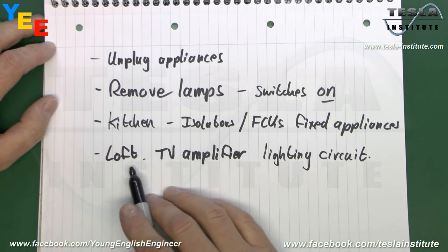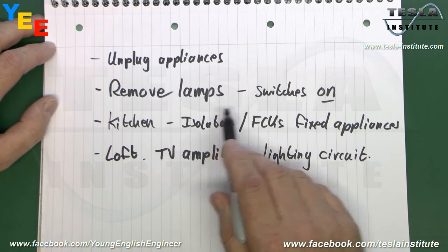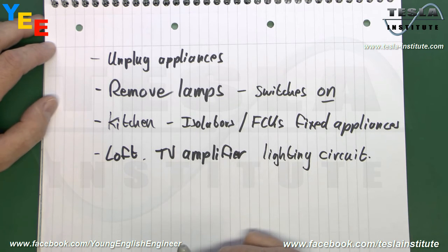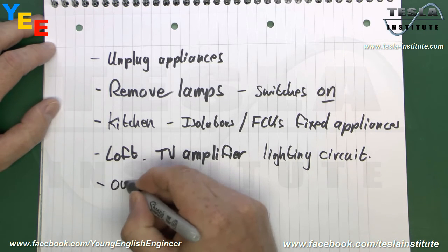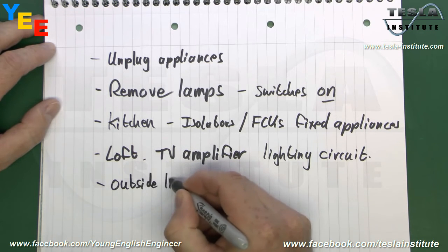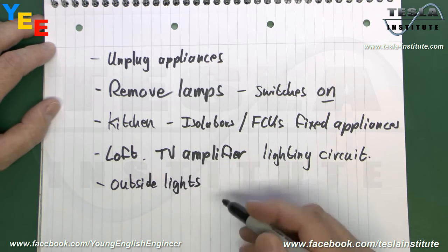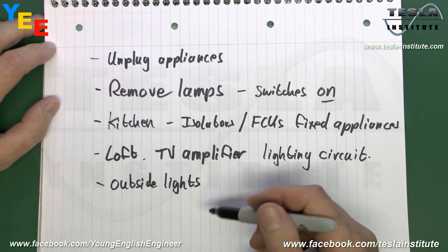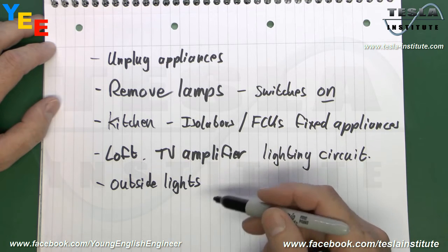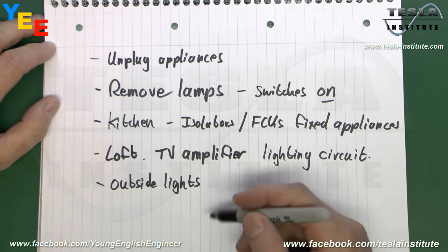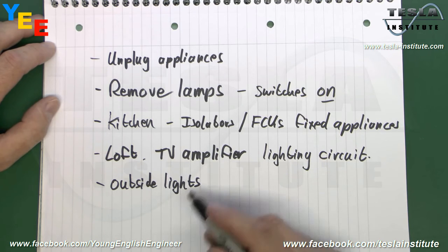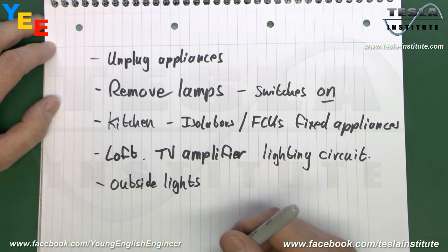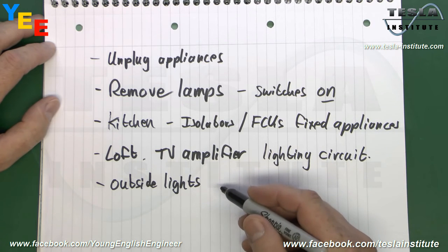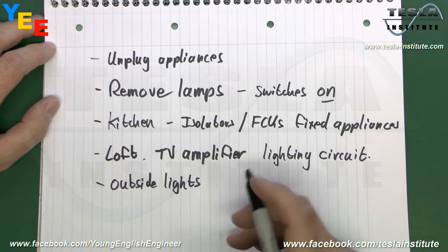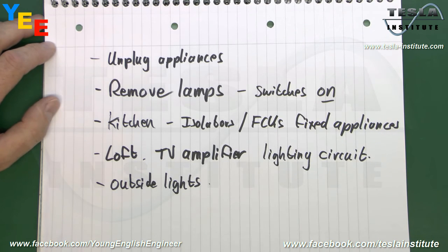And of course there may actually be lights in the loft as well, which may need to have the lamps removed and the switches put in the on position. And other things to look for are outside lights, typically connected to whichever circuit happened to be nearby, and they may or may not have some kind of isolator or switch. Ideally they should have, but again, it's not unknown to find these things where you've got the outside 500 watt beam blinding everybody in the neighbourhood, and somebody has just literally shoved the flex straight into the back of the socket. So completely unacceptable, but these things do happen. So have a look around outside to see what kind of things may be on the exterior of the building.